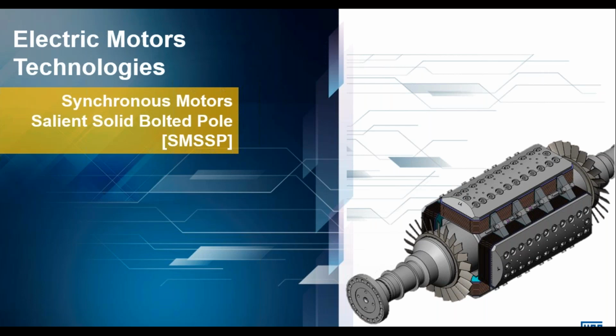Because the cost of the solid integrated pole design is so high, there are alternatives that have been proposed or that are being manufactured, which have similar characteristics but are a little bit cheaper to manufacture. This is an example of one of them. Instead of having one solid block machined from that one solid block, the pole shoe is bolted on as a separate piece of steel to complete the construction. One of the issues with this design is that the eddy currents are exacerbated even more so than on the solid salient pole shoe because of the additional edges of the bolts and the holes, and that produces an extreme thermal increase during starting. In fact, the surface of these pole shoes can reach temperatures of 500 to 600 degrees during starting.